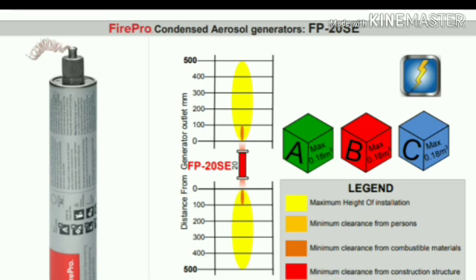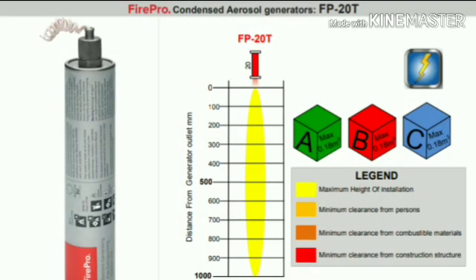Generator coverage constraints: minimum height 0.45 m, maximum area 0.55 m². Maximum height of installation: 1 meter — remember, maximum height of installation for this generator is 1 meter. Minimum clearance from person: 100 mm. From combustible materials: not required. From generator casing: 6.4 mm. This completes the procedure for the FirePro FP-20SE generator. We will now go to the next one.